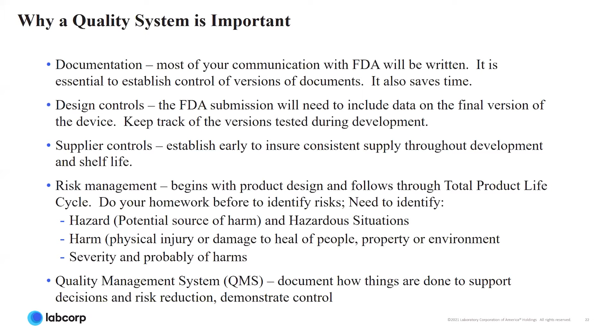So this is from 2020. When FDA does their inspections, they do provide a list of their findings. So you'll see a lot of the findings are about inadequate procedures on that quality system side, that maybe you're not handling complaints. The MDRs, again, that complaint procedure, lack of control. So you'll see a lot of the findings that FDA would have if they come to inspect you are all under the quality system procedures being in place.